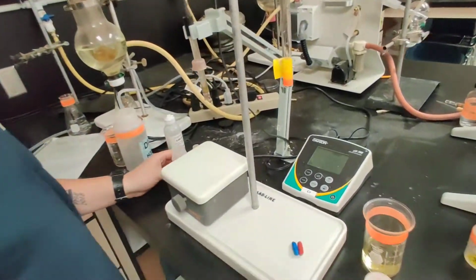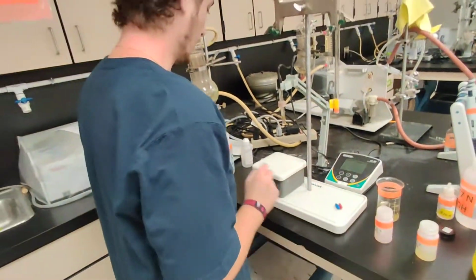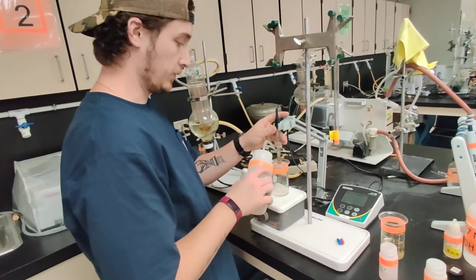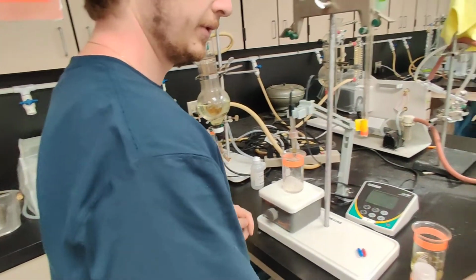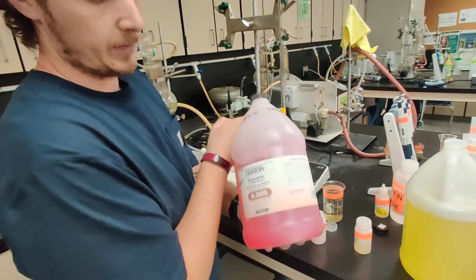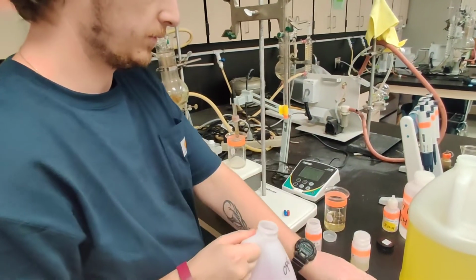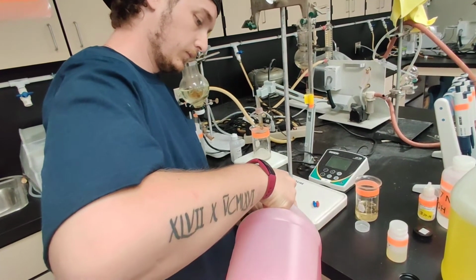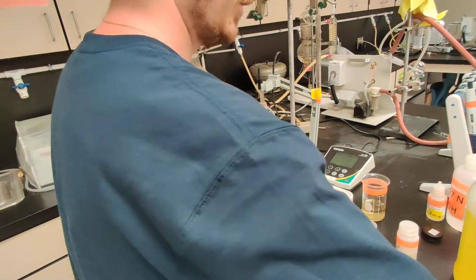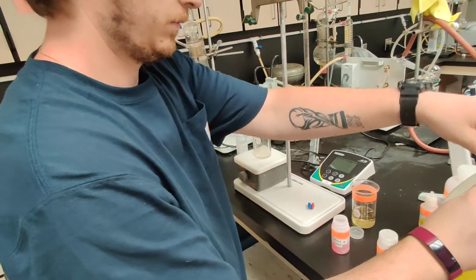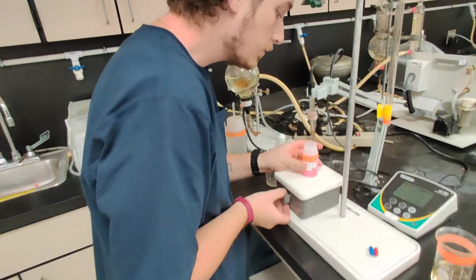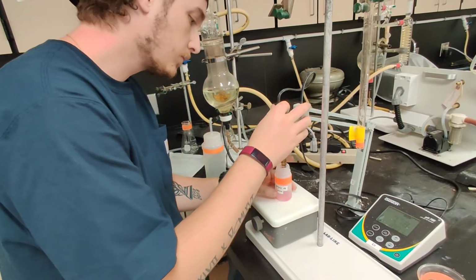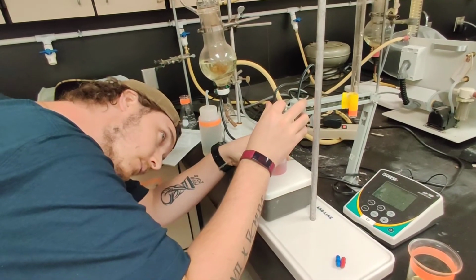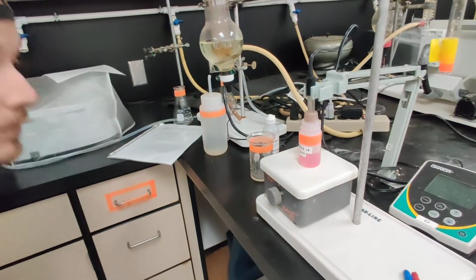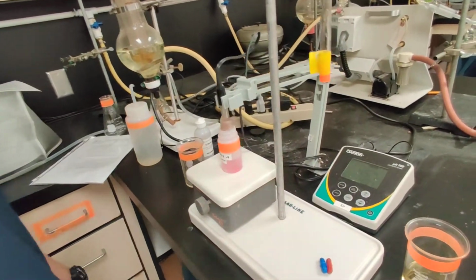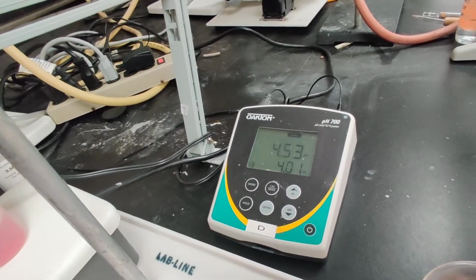Now it's asking for pH 4 or pH 10 buffer. We have pH 4, so that's what we'll work with. Let's give the probe a quick rinse. Perfect. We'll take our pH 4 solution. Same thing, you don't need too much of it. Same thing, make sure the probe is fully submerged in the buffer solution, but it's not hitting the stir bar. And then wait for the ready.